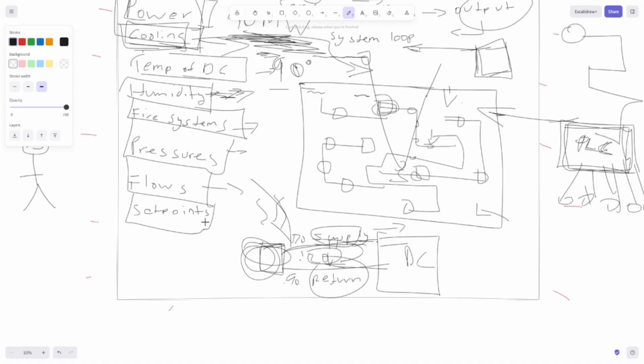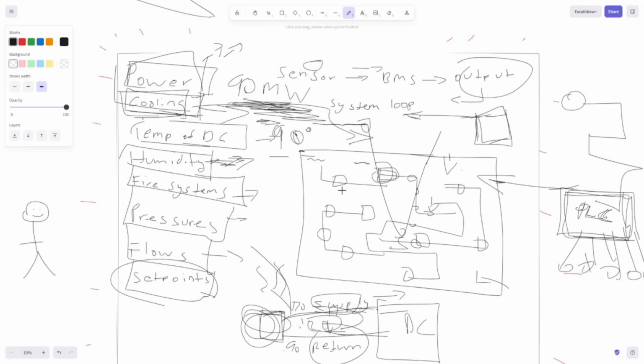As I said, flows as well, and then set points. Set points, so the BMS can be an automatic system, right? So set points is what you set on the BMS, and you tell it, hey BMS, I want my temperature for my data center to be 90 degrees. If it goes over 90 degrees, let's say it goes to 93 degrees, it sends a message out to the logic controller. The logic controller asks, yo, sensor, what are you reading? 92 degrees. And then the logic controller is like, I bet we got rules from the BMS telling us we need to be 90.